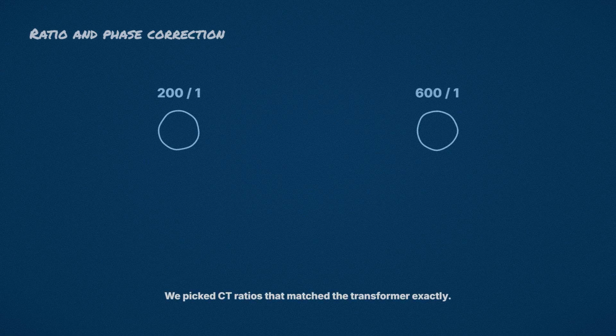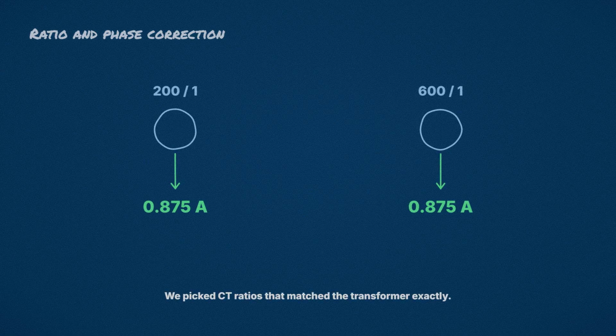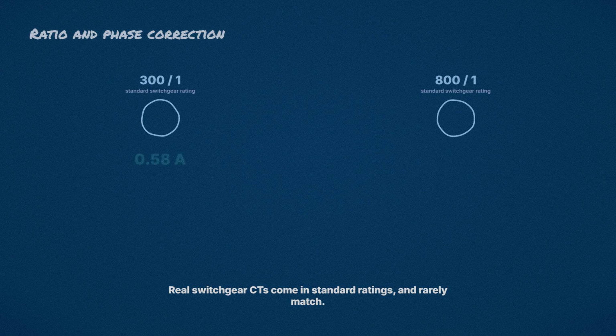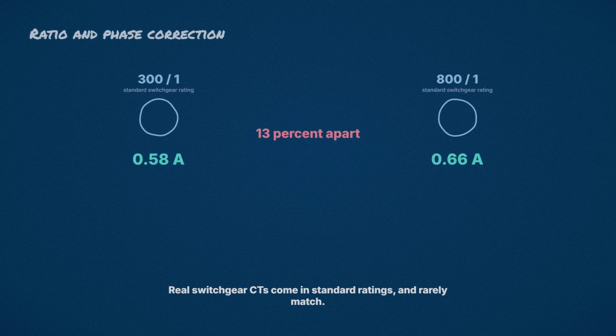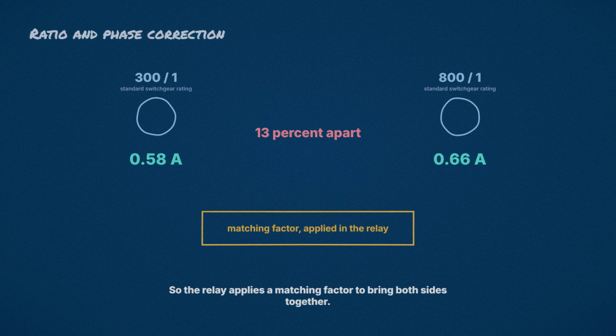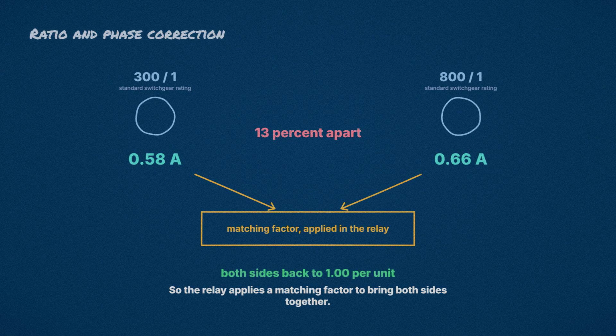We picked the current transformer ratios to match the transformer, 3 to 1, and the two copies landed neatly on top of each other. Real life is not that tidy. The current transformers come from the switchgear in standard ratings, and they rarely match that well. So the relay applies a matching factor to bring the two sides together.